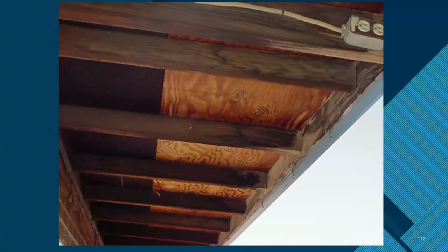Okay, here we are underneath the eaves, and we're taking a look up, and we can see they put new plywood in at some time, but all these old stains here. Here's a receptacle. Harris, you're all excited again. What's wrong with this receptacle and that exposed wire that I can touch? You have exposed Romex, not protected properly, and a non-waterproof electrical box.